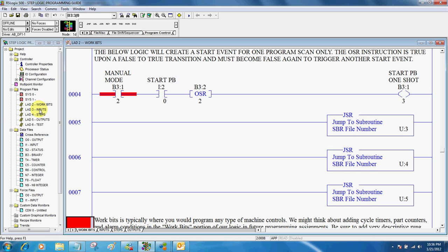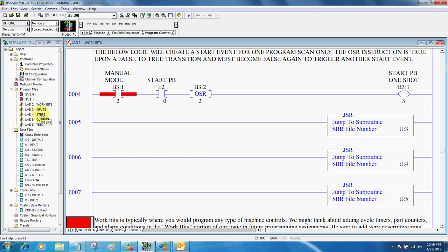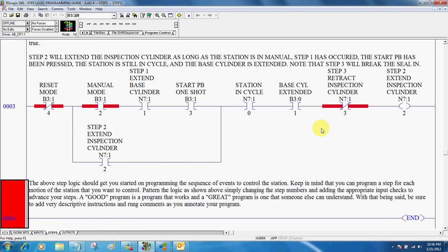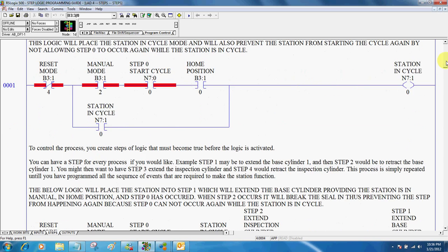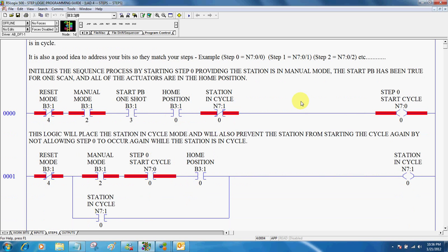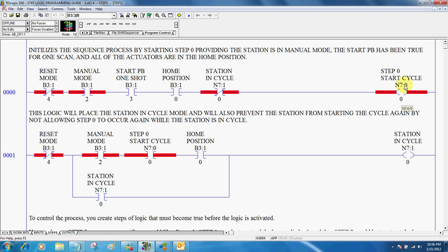So after we've programmed our inputs and our work bits, next thing is to program our steps. And our step logic is really nothing more than a series of events that we want to control. One thing that's important is to be numerically correct. I typically always start off with a step zero. And notice I've used an N7 colon zero bit here. You could use B3 colon zero zero. But the key is to have the zero match the step.